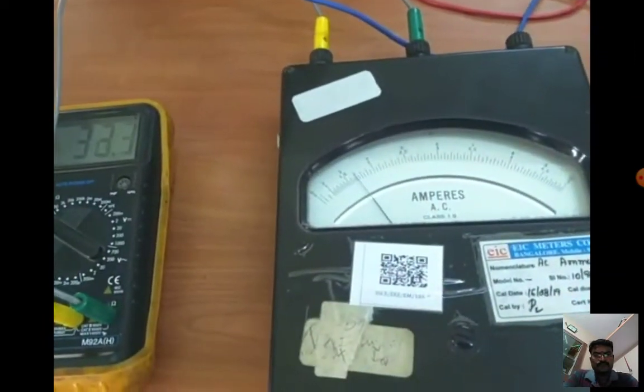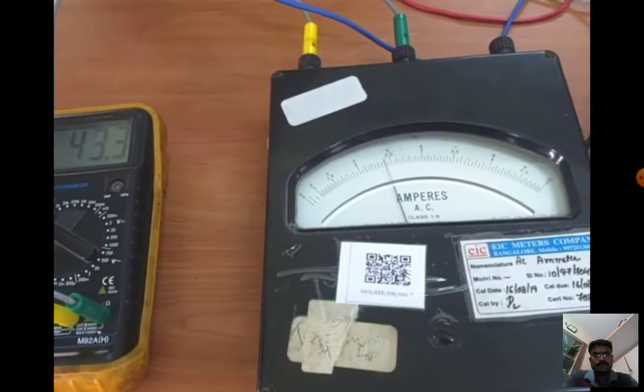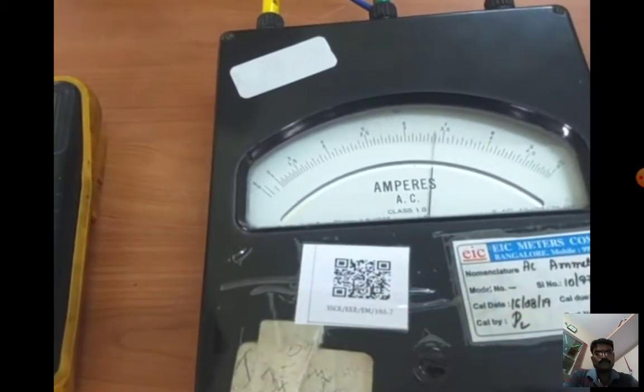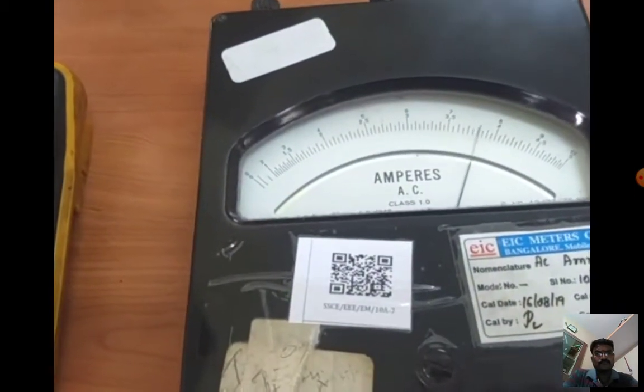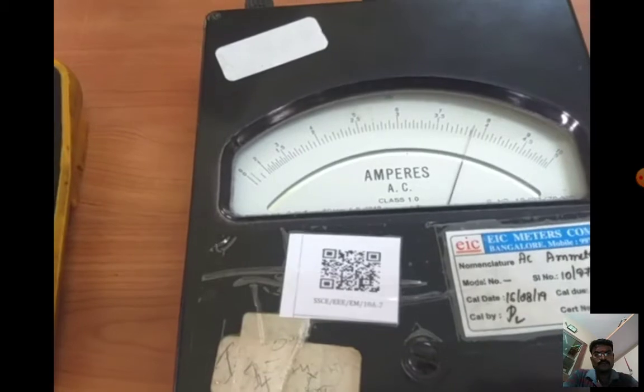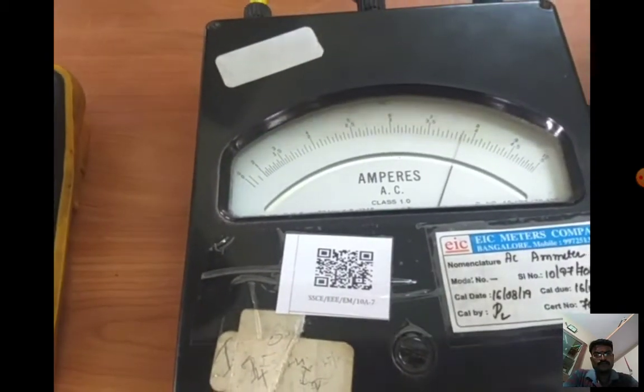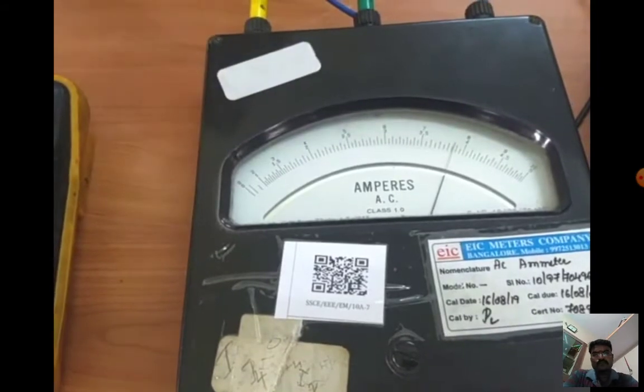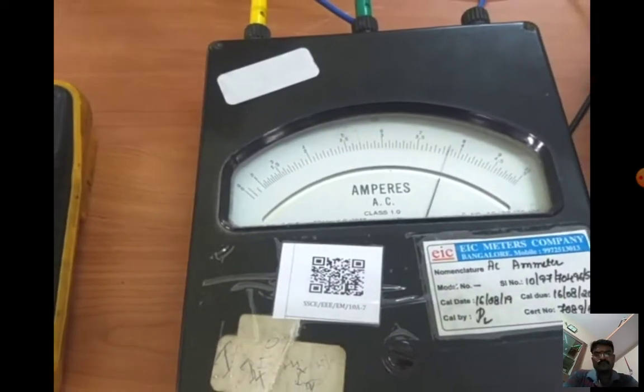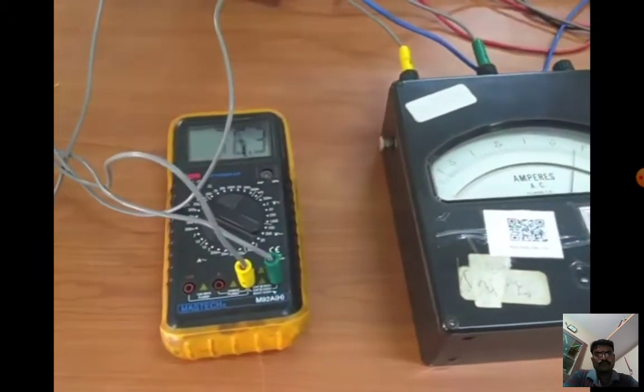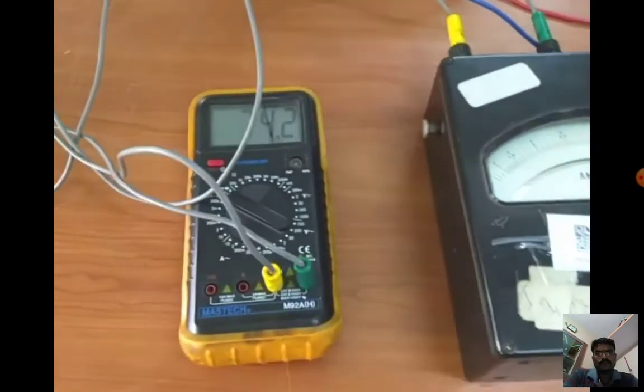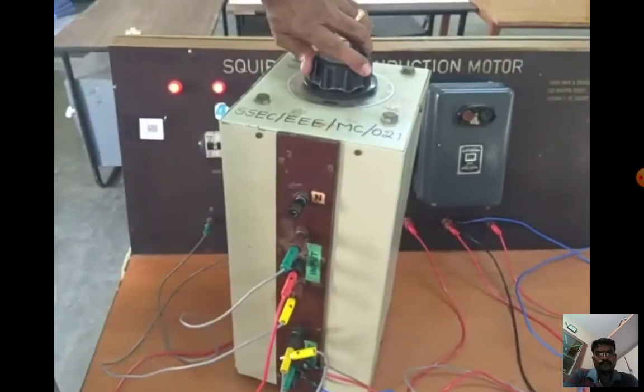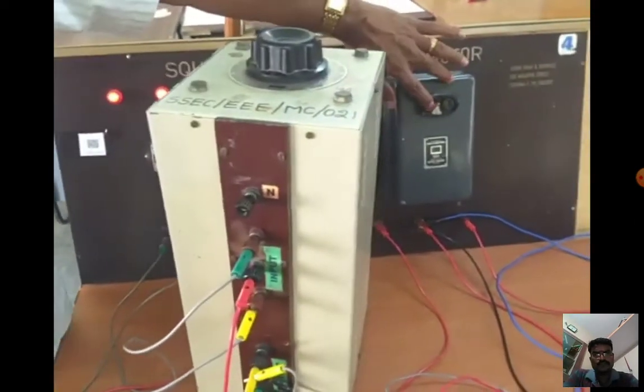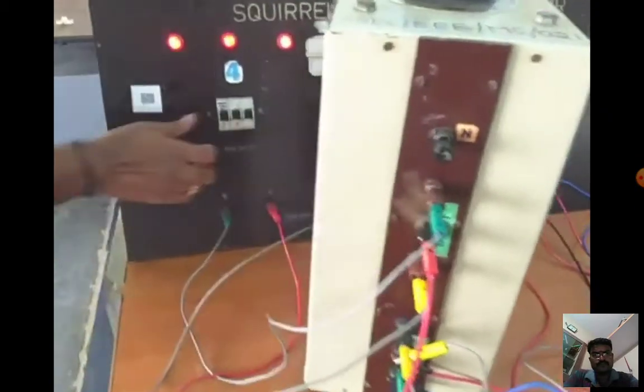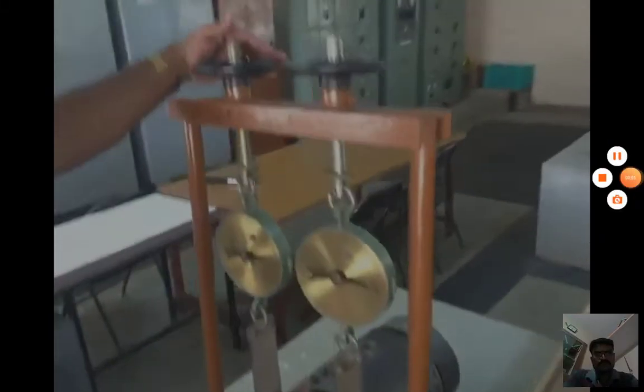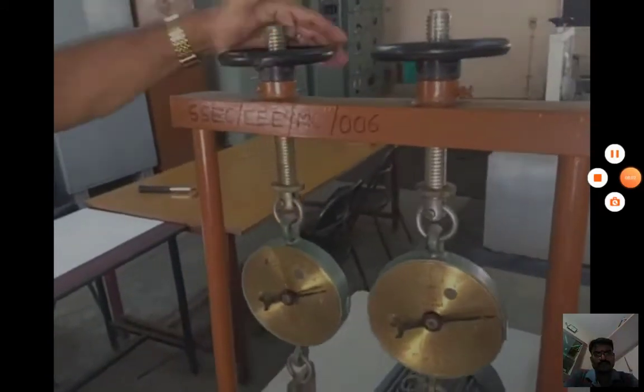The corresponding voltage value we should measure, and the current should not go beyond 8.2 amps. Once it reaches that, measure the corresponding values of wattmeter 1, ammeter, wattmeter 2 and the multimeter that is used for voltage. Then reduce the voltage of the autotransformer to the minimum position. Then switch off the DOL starter and switch off the MCB. And once you have completed, you must release this load.